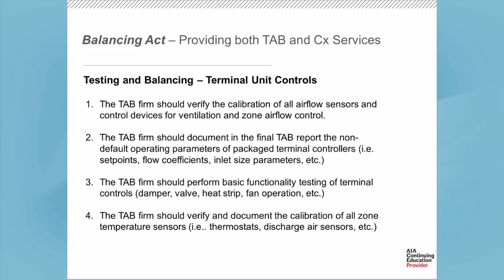Backing up to the actual air handling unit system, or even the pumping system in this case, if it's a large chilled or heating water system, what should the TAB firm do with respect to the overall system? Okay, they are the ones that have to test the total flow or total design flow, if there's diversity and things like that, in these large variable volume systems. So they need to determine the maximum and minimum operating pressures based upon the requirements to achieve airflow at the most remote terminal units. They're the best person to do that. And oftentimes they're called out in the specification to do that. We don't feel like that's a commissioning provider's function. The commissioning provider needs to test it during the functional performance test, but the TAB firm needs to determine the set points and work with the controls vendor to do that.